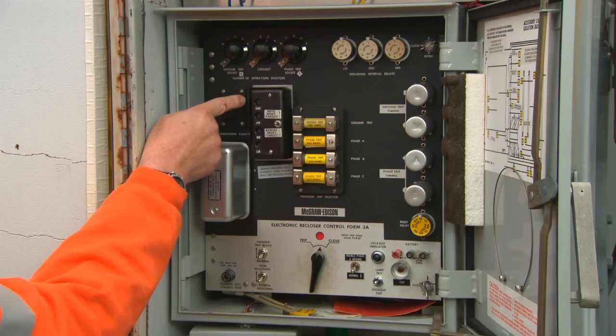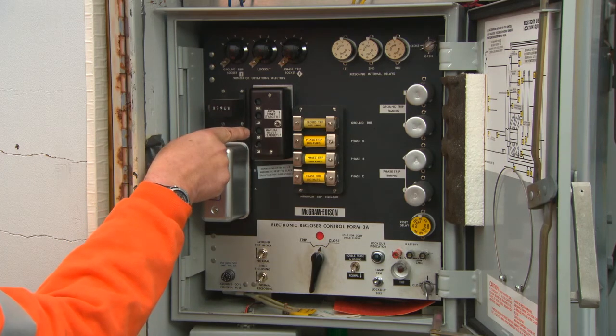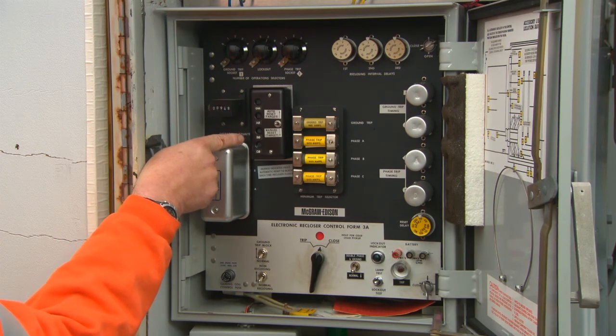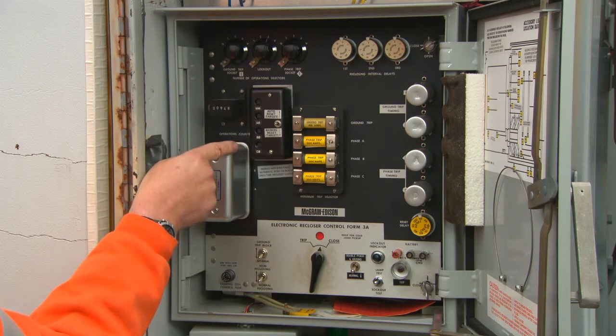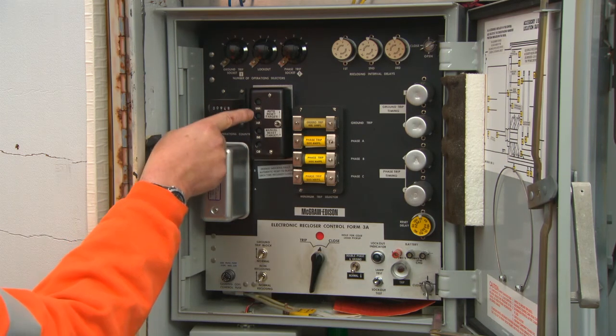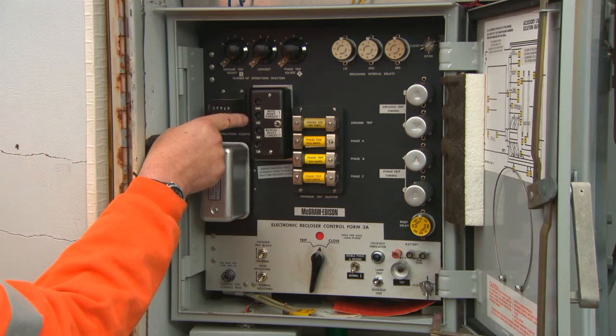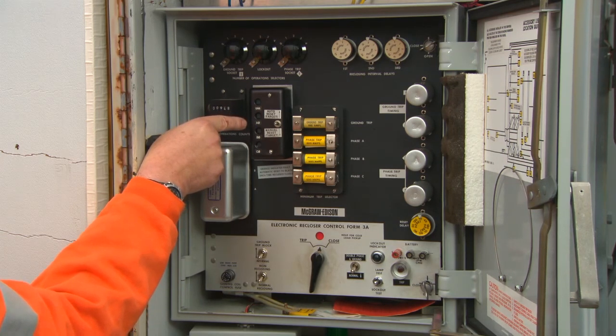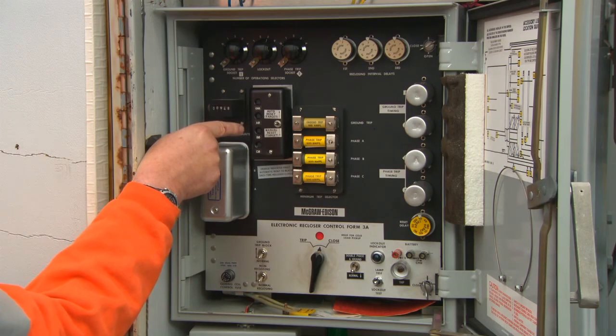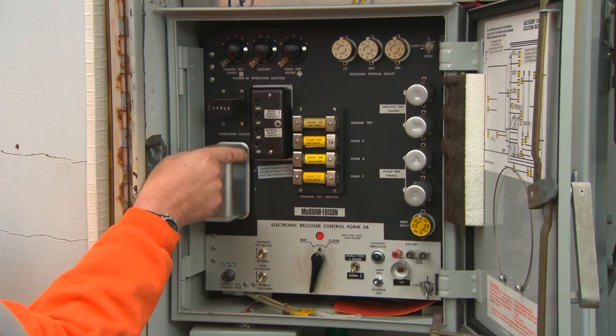Turn clockwise to close, counterclockwise to open. The indicator above the handle is red for closed, green for open. If the recloser trips, the indicator will turn green. Below these, we have the target indicators. This has status indicators for ground, A phase, B phase, and C phase. Upon tripping this recloser and when set for auto reset, these will display while tripping. Upon lockout, this setup will remain. By moving the toggle switch to manual reset, you can reset these targets.